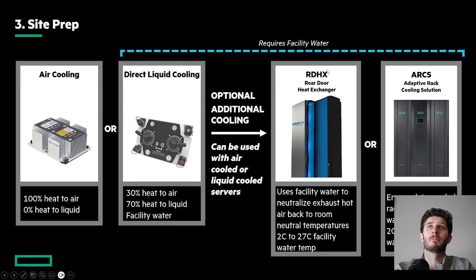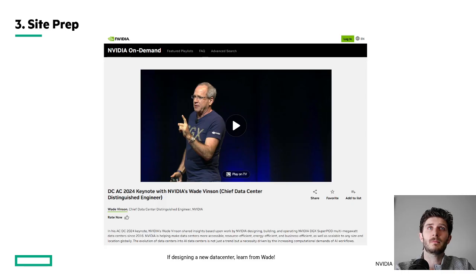In practice, we end up combining a lot of these technologies, using direct liquid cooling to cool most of the system, and then some combination of air cooling, rear door heat exchangers, or ARCS to get the rest of the heat out of the system.